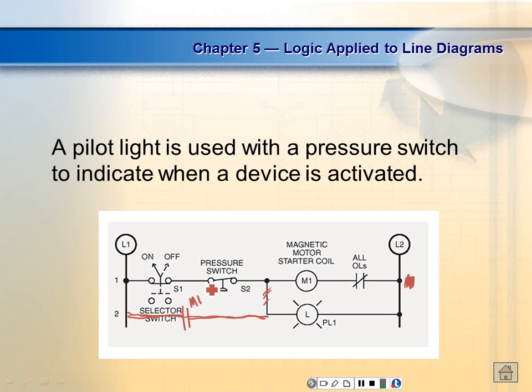We have devices like that, which would have a set of contacts in. The motor comes up, well, it's showing it's running, but the motor's not actually running. That doesn't indicate the motor's running. All that indicates is the contactor that controls the motor should be energized. Of course, you got to understand, if this guy right here went bad, the light would come on. So that would be the advantage of doing it this way. If you do it this way, the relay itself could be defective and the light still comes on. So that's a good point. If the contactor contacts were bad, but the contactor still closed, the light would come on also, right?